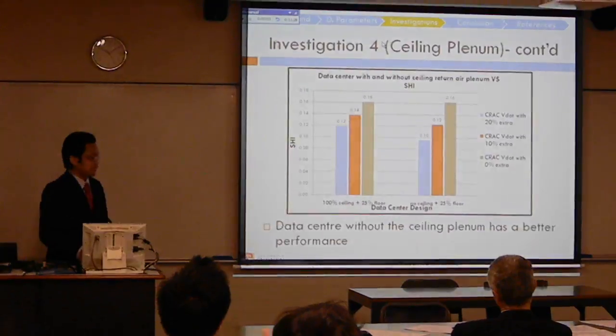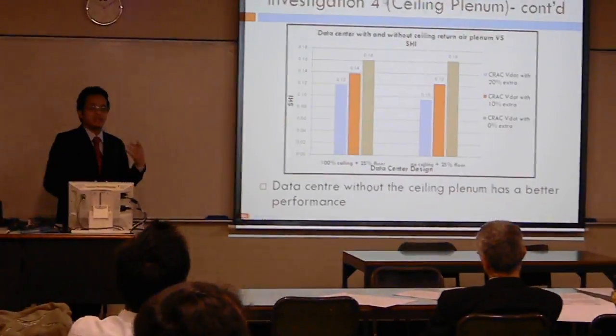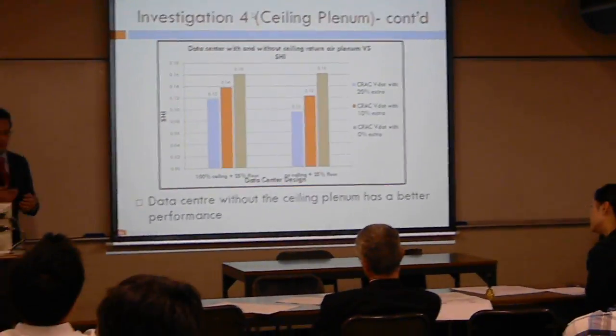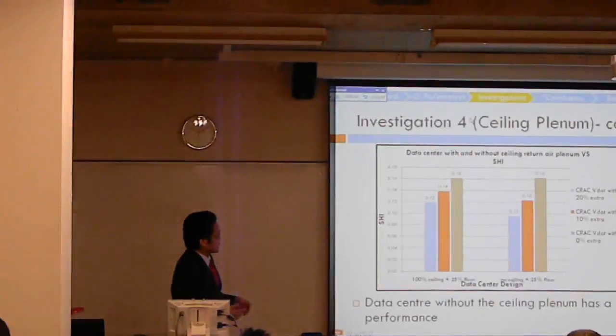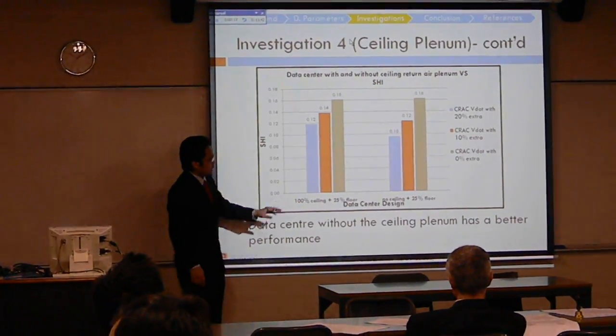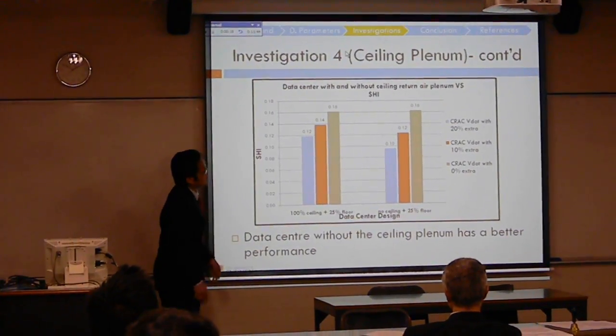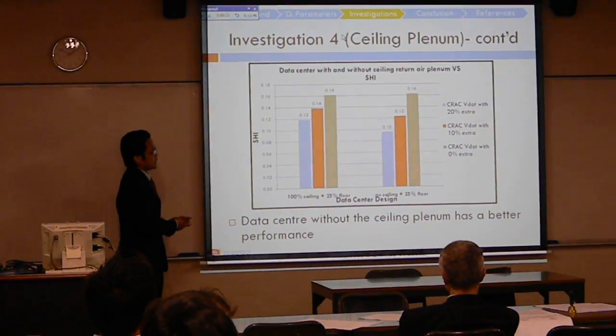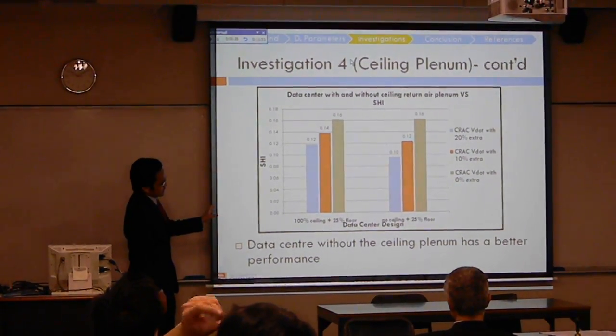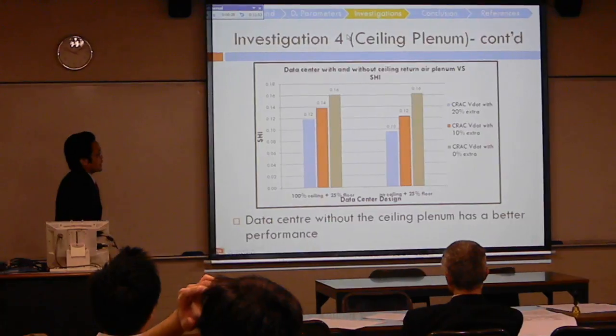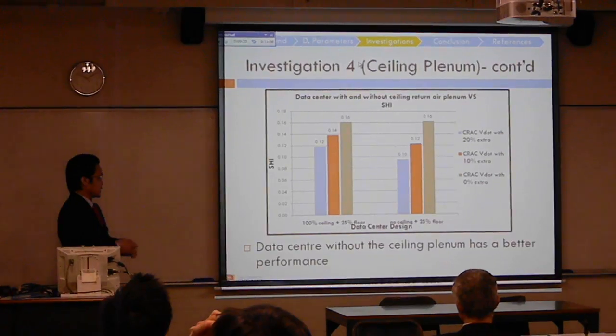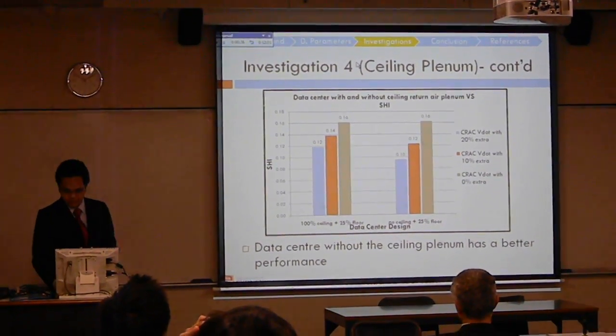This is the comparison — I would like to see whether a data center with a ceiling return air plenum will give benefit or not. I compared the left-hand side, which is the data center with the ceiling, against the data center with no ceiling. Surprisingly, it turns out that the data center with no ceiling shows better, with a lower amount of SHI. Therefore, I can conclude that a data center without the ceiling plenum will have better performance.